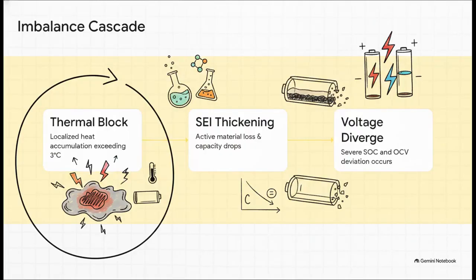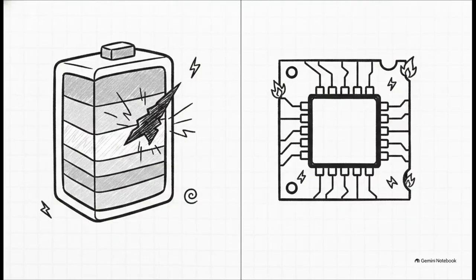It's a cascading failure, reacting like a ticking clock. It usually kicks off with a physical roadblock, like a patch of uneven cooling paste that creates a thermal dead zone. Because of joule heating, the heat gets trapped there. And if the temperature difference between cells exceeds just 3 degrees Celsius, well, the laws of chemistry take over. According to the Arrhenius equation, all that excess heat causes the cell's internal SEI film to rapidly thicken. So you lose active materials, the capacity drops, and boom, you get severe voltage divergence between that hot cell and its cooler neighbors.